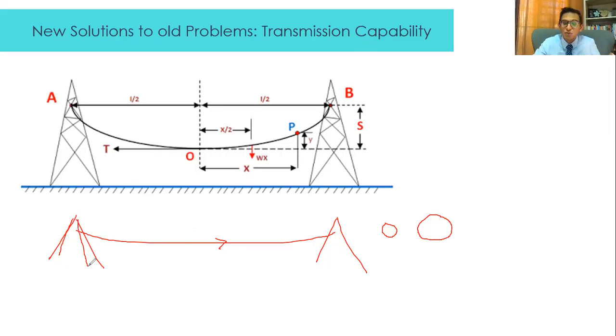So what's going to happen? If we install a bigger conductor, it's most likely going to sag, and the ground clearance is going to be affected. We won't have ground clearance, and the towers are going to be mechanically stressed and can even rupture. So what can be done? How can we increase the current carrying capacity while keeping the legacy transmission line system?